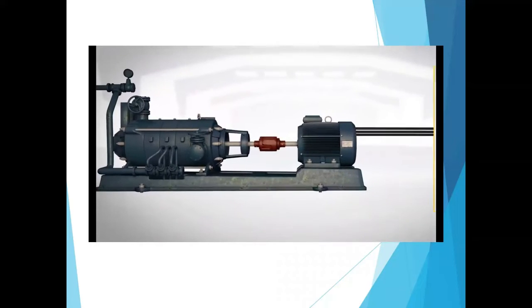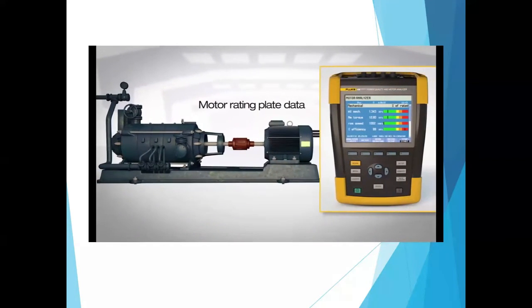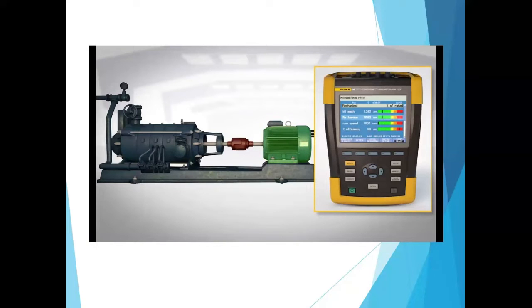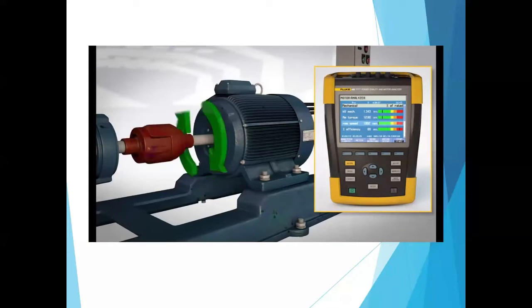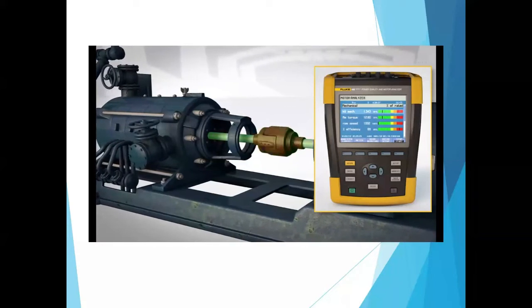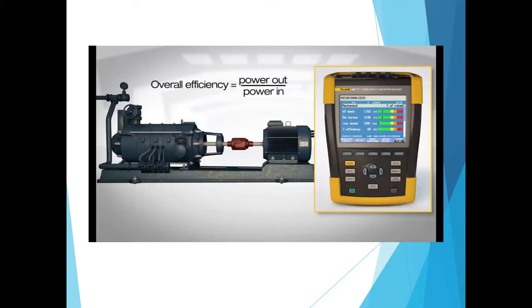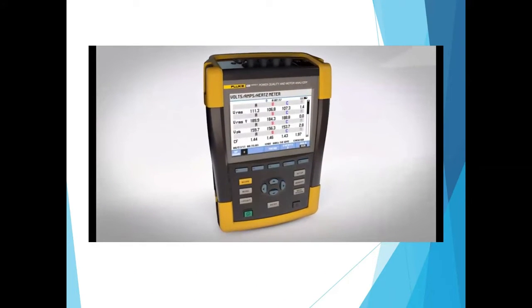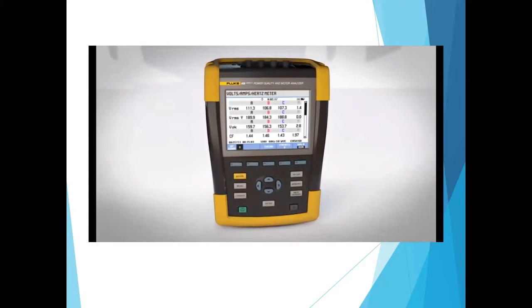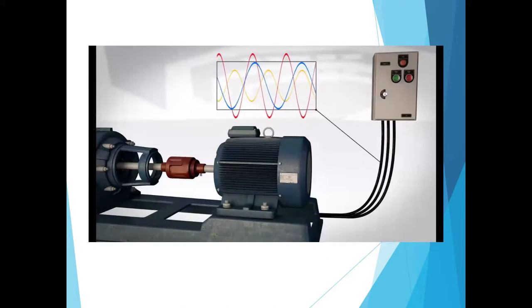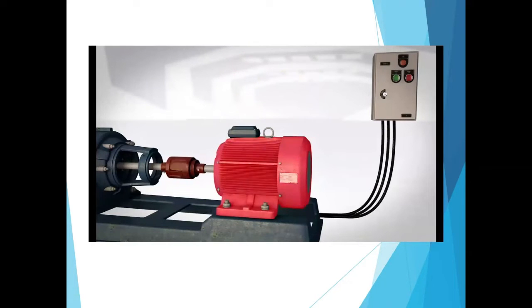Using 3-phase electrical measurements on the input and motor rating plate data, the 438 calculates torque, the most critical mechanical performance variable, speed, load on the motor shaft, and overall efficiency, without the need to install mechanical sensors. All this with a single tool, and all while the motor is running, so you don't sacrifice uptime. Power quality issues, such as unbalance and harmonics, can cause motors to run hot, eventually stressing windings and accelerating failures. Motor failures lead to costly downtime, and the cost of waste associated with inefficient motors adds up.